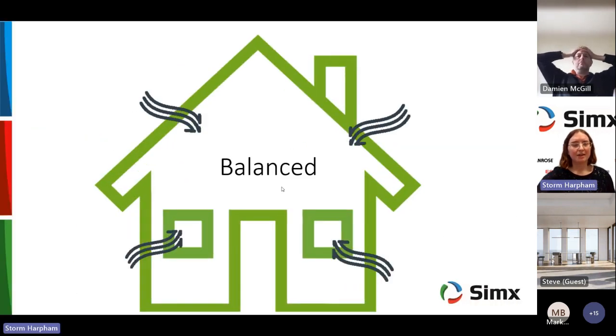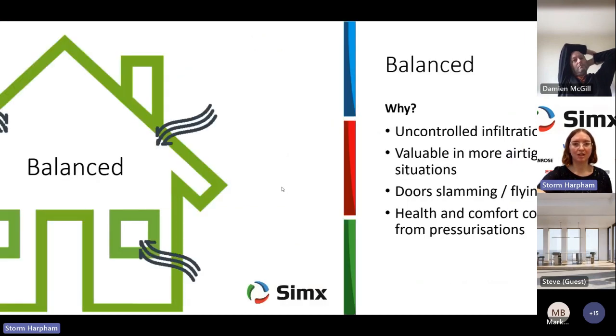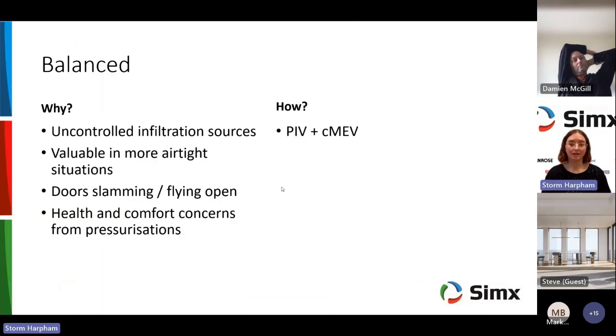From there we get balanced ventilation, which is an interesting solution. Balanced is typically a combination of continuous mechanical extract and PIV, with two clear pathways where you control the air in both directions. You need that well balanced, with actual commissioning to balance the solution.